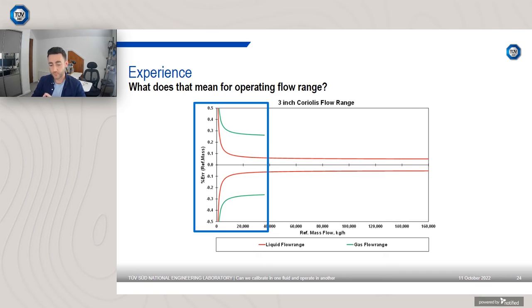Now, when I get asked, what do you recommend? Well, I recommend two things. I recommend, yes, you try and calibrate with respect to your mass flow rate. So I would still try and achieve, let's say, 5 mass flow rates down that low end of the water flow. But I would also try and match up with respect to turn down. So let's say you're operating from 90% down to 10% of the gas mass flow rate range for your Coriolis meter. That gives you a good coverage.